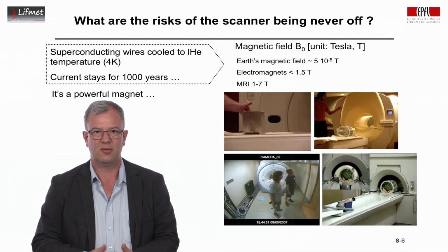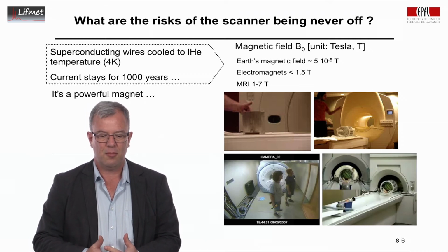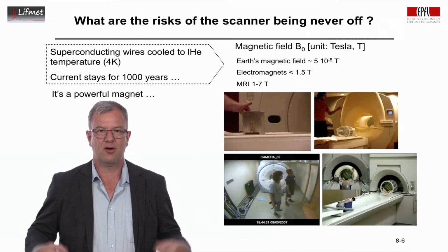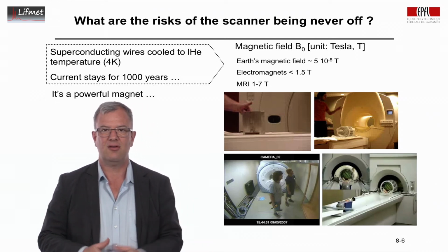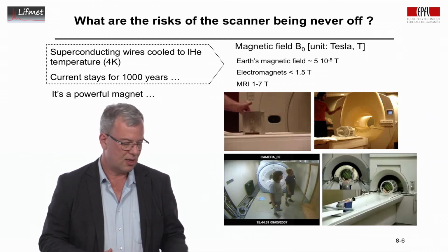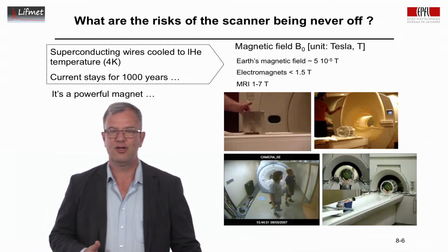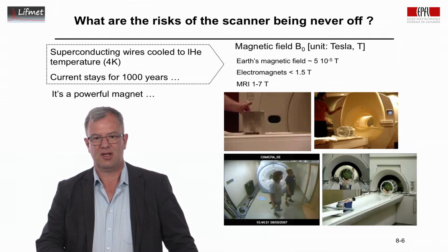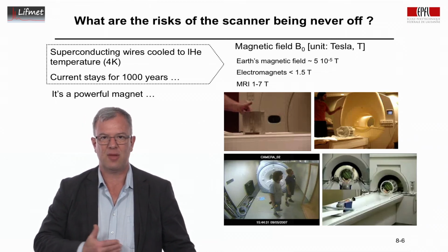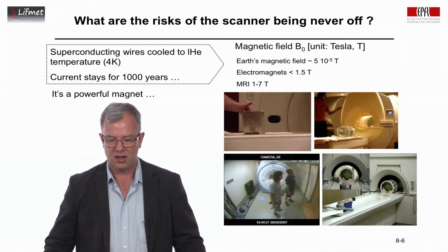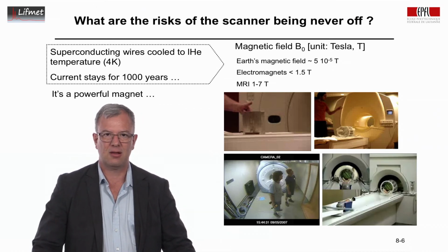It requires specific measures. The measures are to take off all magnetic things that we carry on ourselves. In the case of a medical emergency in an MR scanner, the first reaction is to take the subject out of the magnet and out of the magnet room, and only then start coming in with medical equipment.